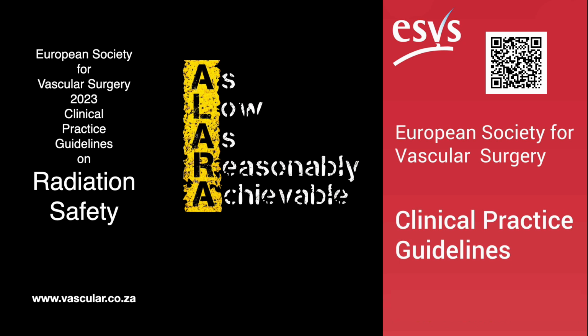Quadrupled the dose? That's huge. It is. So the rule of thumb is smaller FOV equals higher patient dose rate. The system usually automatically collimates the beam to the selected FOV to avoid irradiating tissue outside the displayed area, which is good for reducing scatter to staff, but it means the entrance skin dose in that magnified area is significantly higher. So the advice is? Use the largest FOV possible that allows you to see what you need to see. Use conventional magnification judiciously, only when absolutely necessary for visualizing critical details.